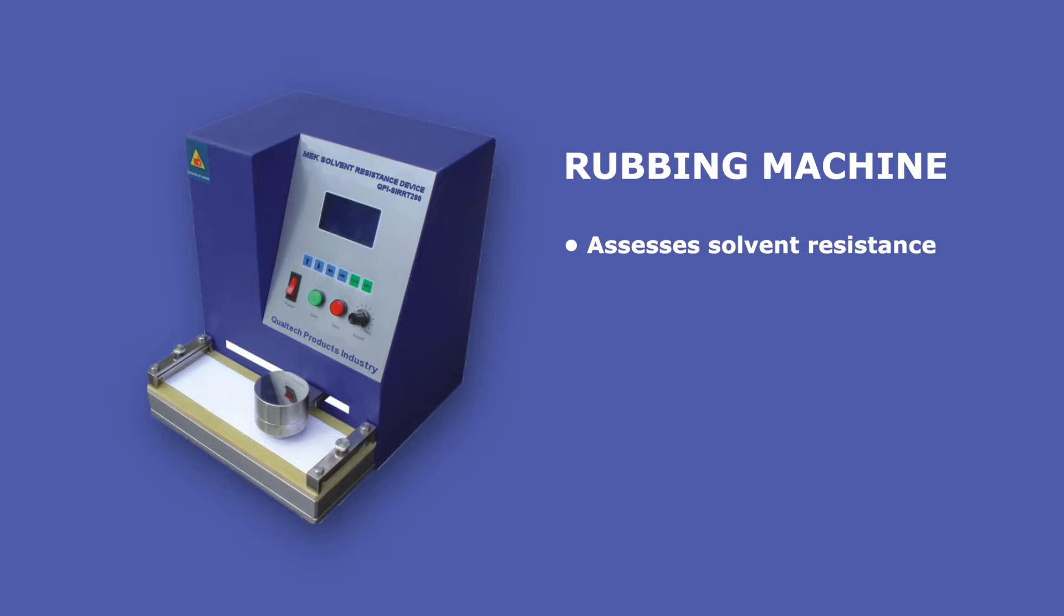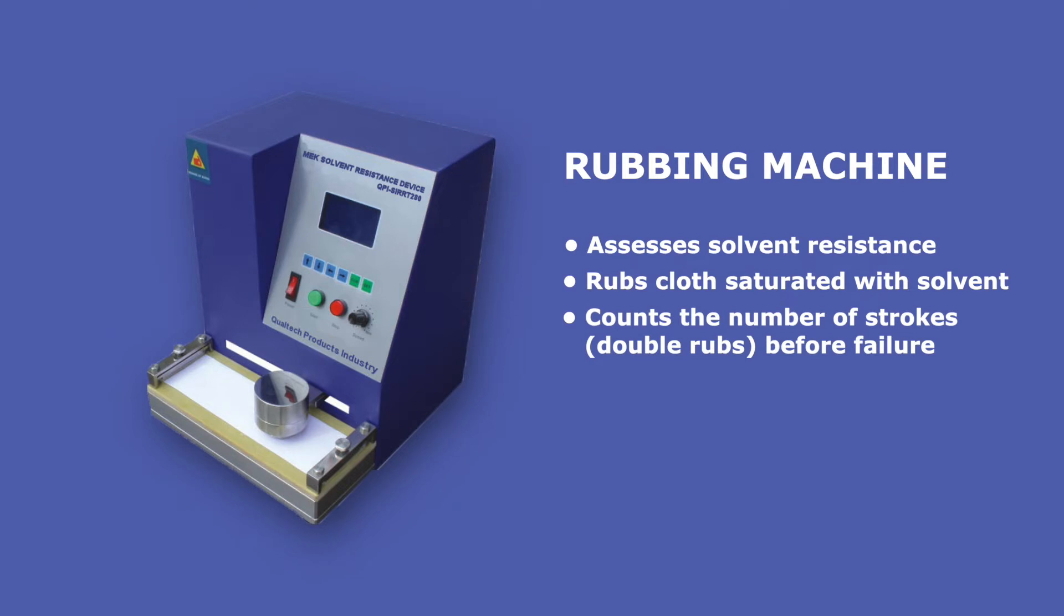This automated machine is used to test the solvent resistance of a coating by rubbing a cloth saturated with solvent across the coating and counting the number of strokes or double rubs before the coating ruptures or fails. A double rub is defined as one complete forward and backward stroke over a coated surface under specific conditions.